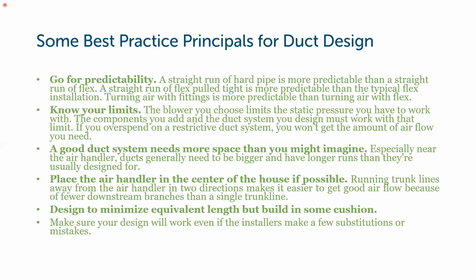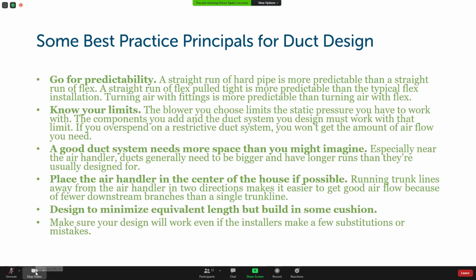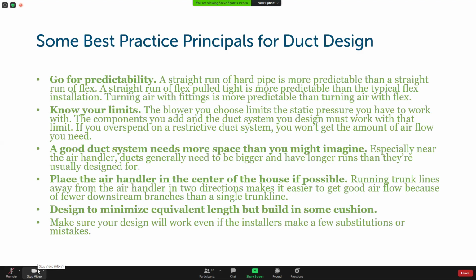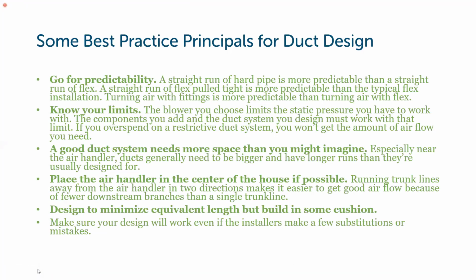So, best practice principles for duct design. As I said, any equipment that moves air, whether it's ventilation equipment or heating and cooling equipment, the unit itself is designed to move a certain amount of air at a certain flow rate at a certain static pressure, but that's just what it's designed to be able to do. The duct system is the system side of it that actually allows that equipment to do its intended purpose. So duct design is very frequently and often overlooked, and the implications of that are pretty significant.